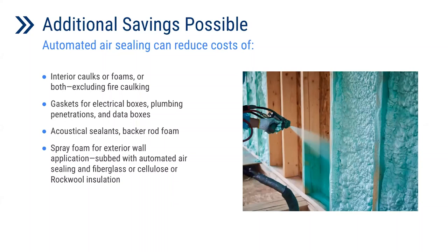In addition to the energy savings and capacity reduction, automated air sealing can have the capacity for additional savings by replacing some materials. This can include interior caulks or foams — excluding fire caulking — gaskets used in electrical boxes, plumbing penetrations, and data boxes, as well as acoustical sealants and backer rod foam. In certain applications, more expensive insulation such as closed-cell spray foam can be replaced with automated air sealing and relatively cheaper insulations like fiberglass, cellulose, or rock wool insulation.